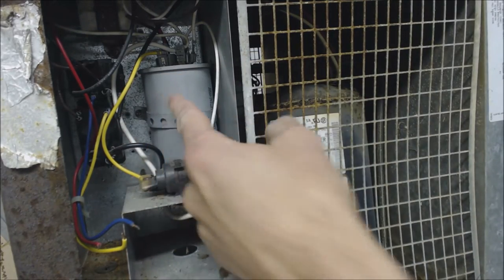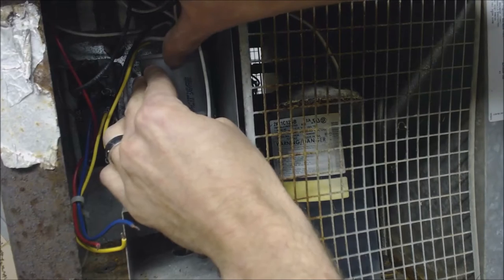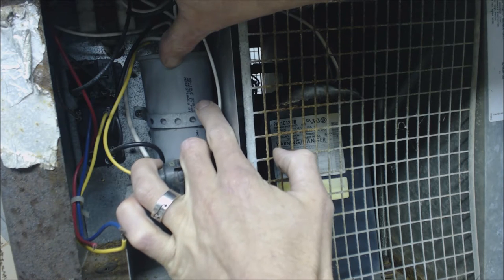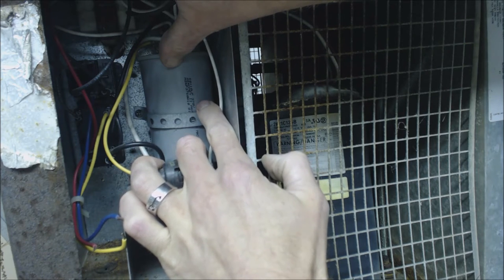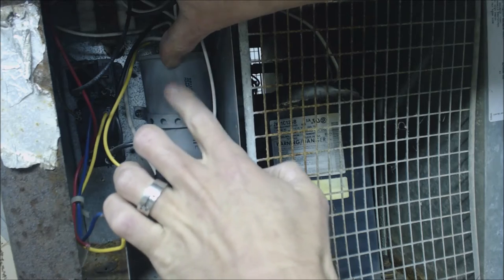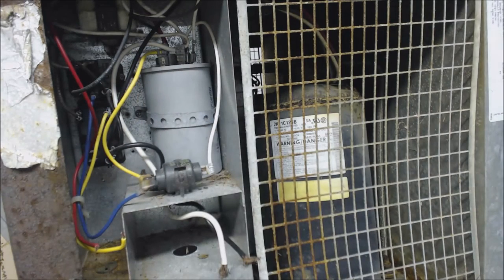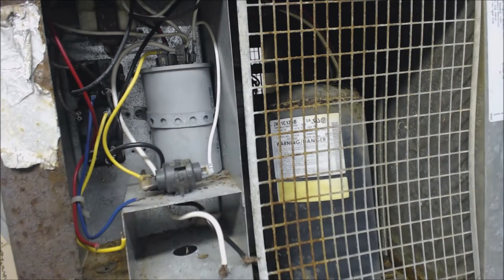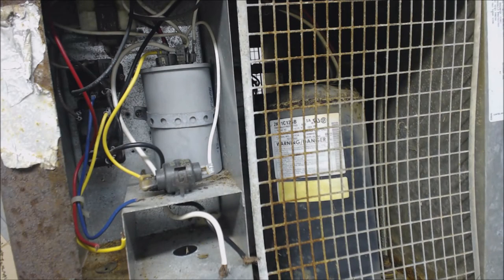Right here you have a capacitor — it's a dual capacitor. This one is a plastic version. It's a 60 plus 10 UF at 370 VAC. 60 plus 10, and UF means the same thing as MFD, at 370 volts. You can replace this capacitor with a normal metal one — it's a dual capacitor with common, fan, and Herm on it. You just replace the wires the same way. I have a bunch of other videos on checking capacitors and checking fan relays if you want to check those out.